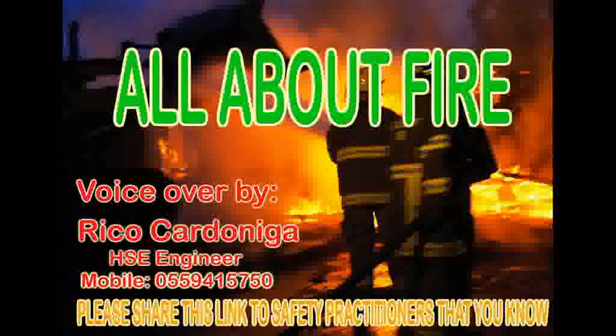The main requirements of a safe means of escape will be, if necessary, two routes in opposite directions, fire-resistant walls and ceilings, adequate size relative to the number of persons, within travel distance guideline, clearly marked direction arrows, emergency lighting, exit routes free from obstructions, final exit door opening outwards, fire or smoke doors en route should be self-closing, fixed stairs to upper floors, exit to a safe place or assembly point.